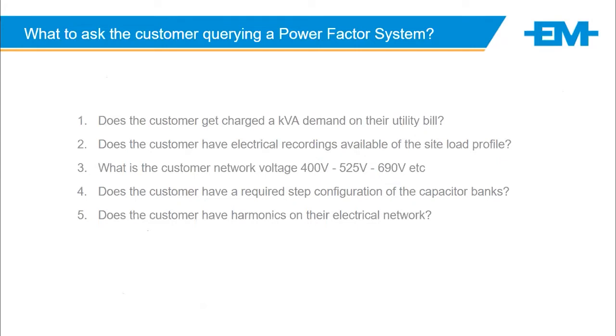So what to ask your customers when querying for a power factor system? The first thing you need to ask them is, does the customer get charged kVA on their utility bill? First point, before you go any further. Then, does the customer have electrical recordings available of the site? What is that? We use power analyzers. We sell these power analyzers. For me to be able to help you, I need to see a site profile. And we get quite detailed on this. I need a lot more than just volts and amps, because I will be able to identify if there are any other site issues for you.